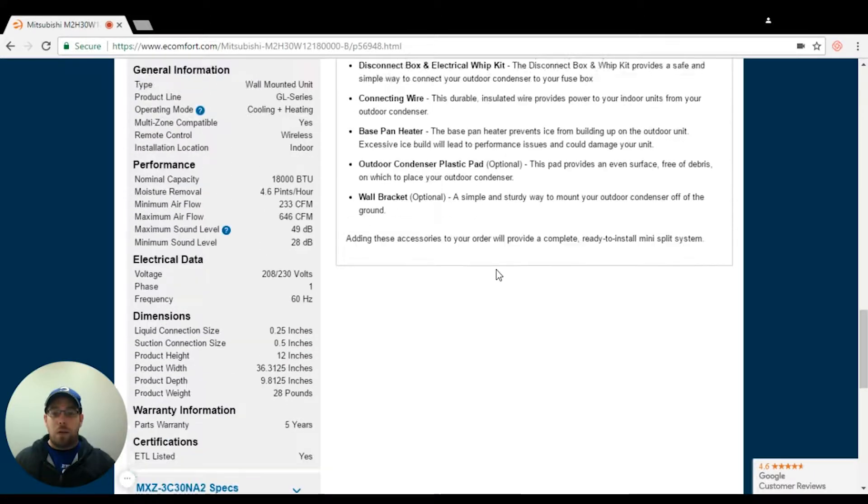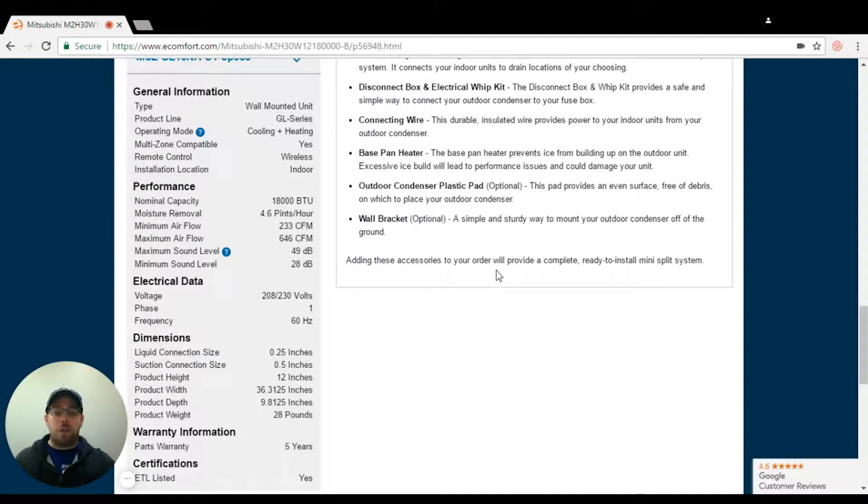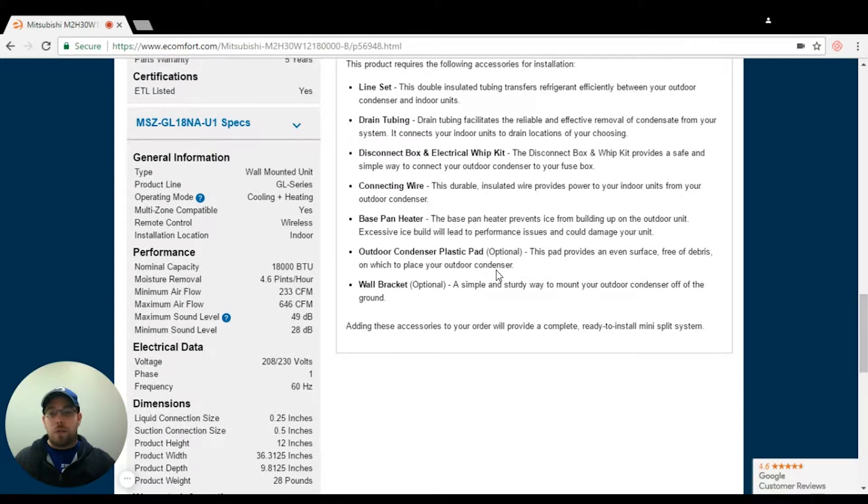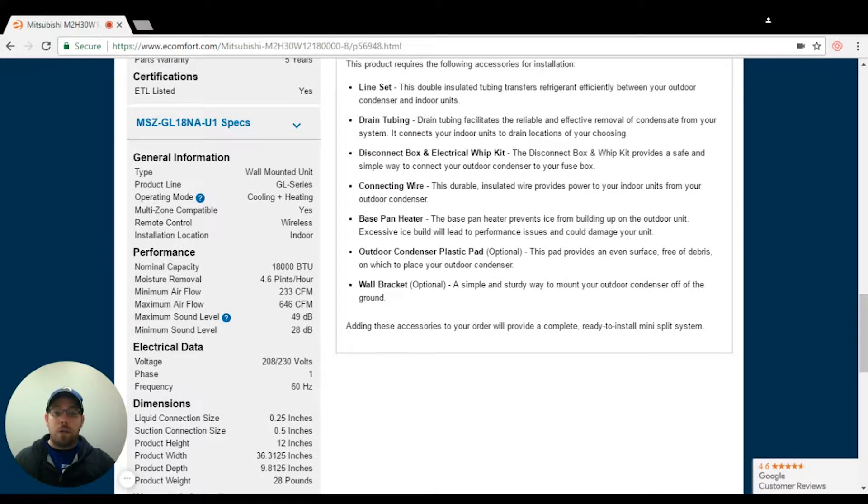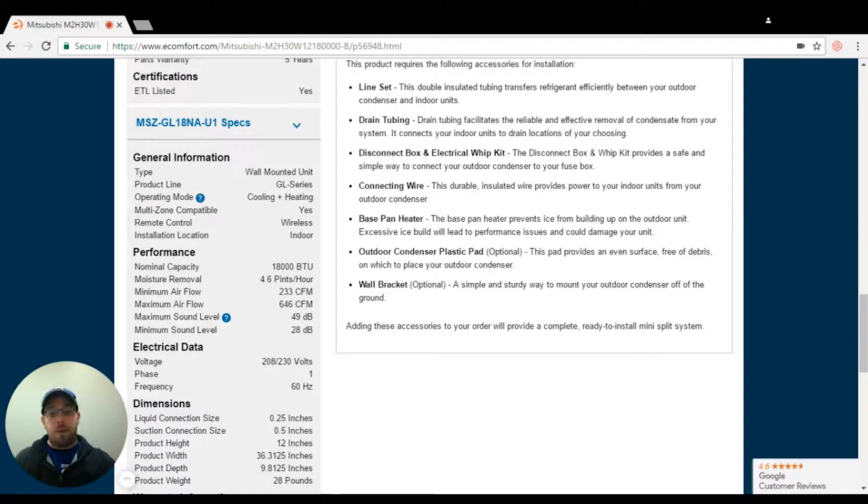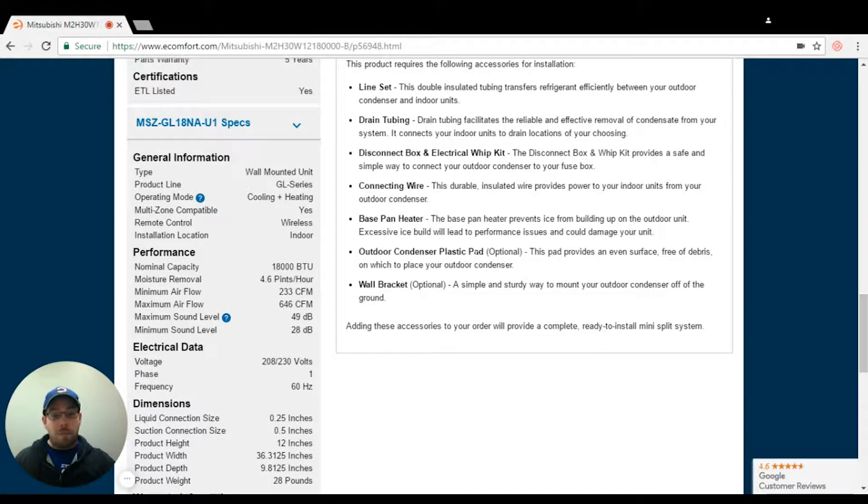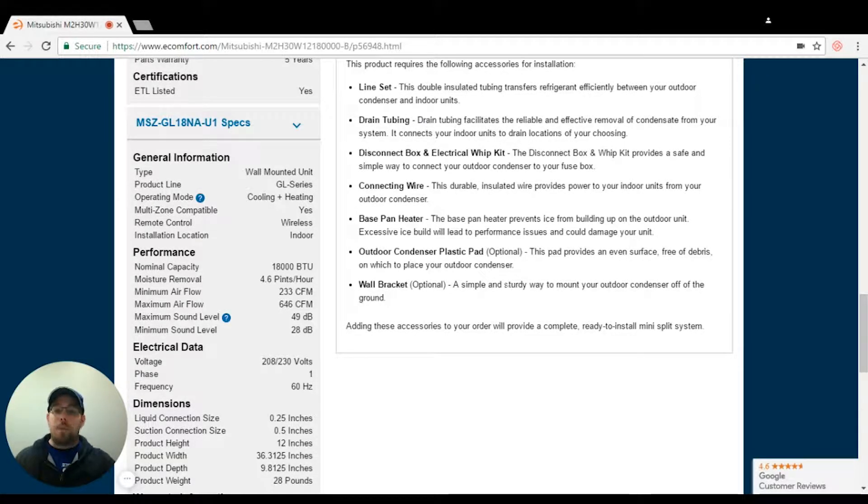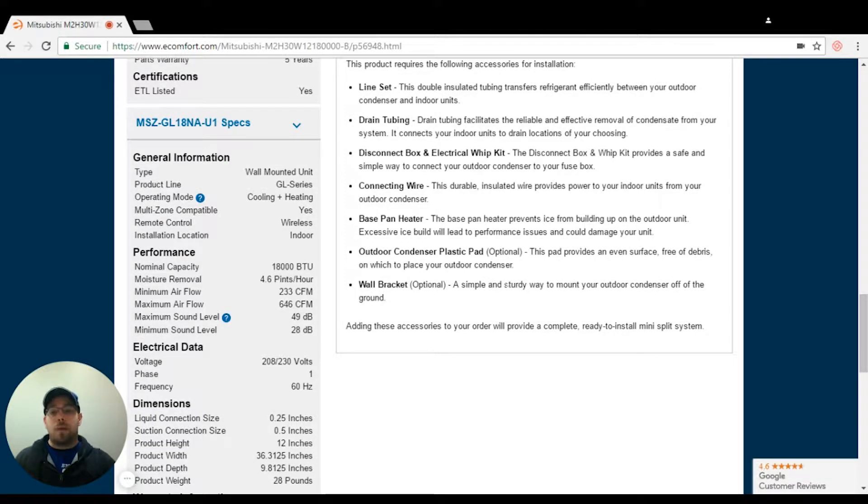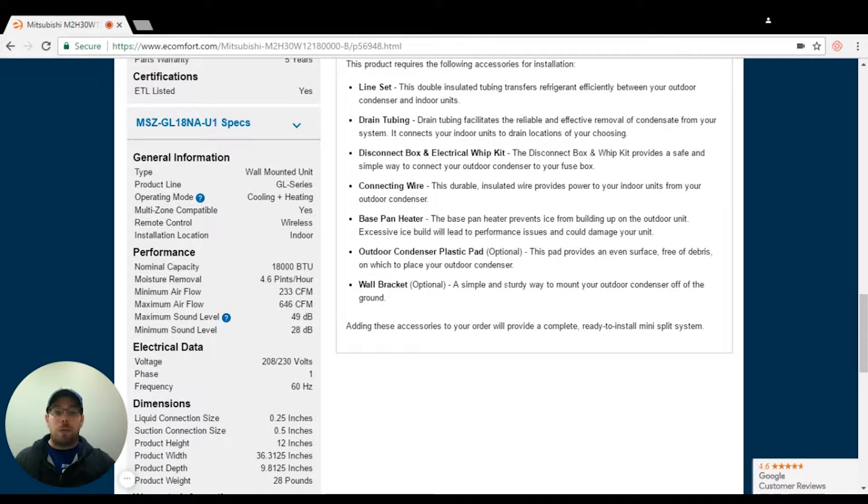Now different brands are going to show different sizes, so always make sure that you double check. For instance, for an LG single zone system, it might be three eighths by five eighths for an 18 or a 24. But when you do a multi-zone system, it might require a quarter by half. Always make sure you or your installer go back to the installation manual to double check.